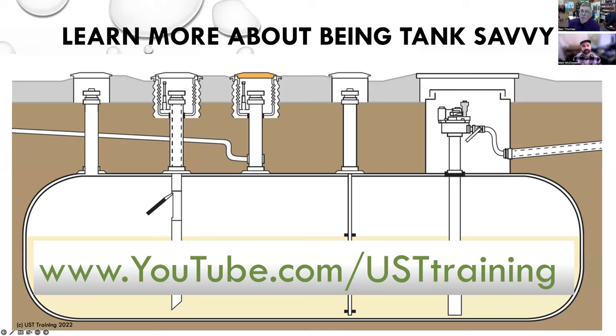Marlon, that's a case where, when we talk about underground storage tank questions, and we get them all the time, the answer almost starts off, well, Marlon, it depends. It really depends on a lot of things. At a minimum, if you have a single wall tank, you have to do a leak test every 30 days, 0.2 gallon per hour. If you have a double wall tank, you're doing leak detection 24/7, 365, so it kind of doesn't matter. So the minimum would be proving it every 30 days.